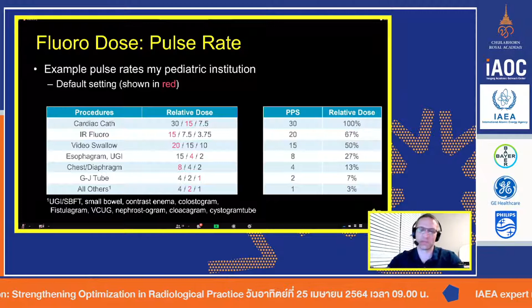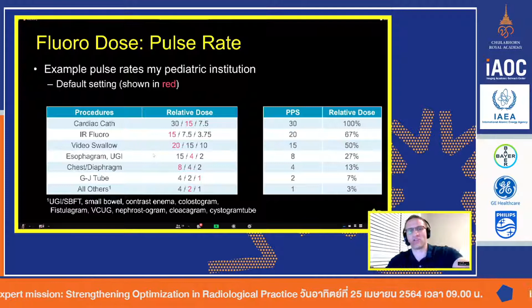Other vendors, I can speak for Siemens, for example, you can go from as low as 0.5 pulses per second all the way up to 30. You would just open up a different window on your table side system and push a couple buttons and boom, the world is your oyster on this one. You can do all the pulses you want. But in most places, you're going to set it up so you basically have 3 options. And why and how you choose those 3 options really just depends on working with the radiologist.